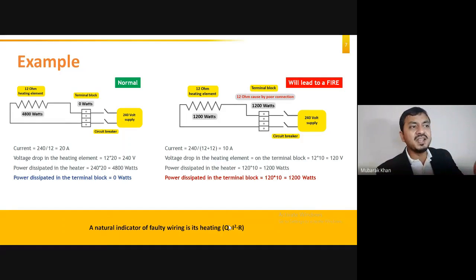So here in this case we have taken the resistance of the loose connection as 12 ohm just for simplicity. So 12 ohm loose connection at the terminal block, 12 ohm heating element. So the voltage will be equally distributed between the two. Okay, so there will be 120 volt voltage drop at the terminal block, and 120 volt voltage drop at the heating element, right? So power dissipated will also be equal on both. So if you calculate it, around 1200 watts of power will be dissipated on the terminal block and the same amount of power will be dissipated on the heater.